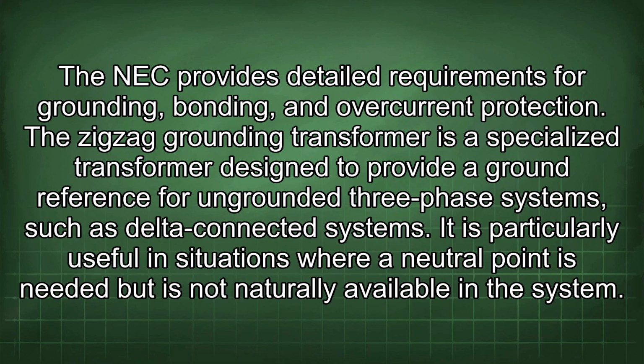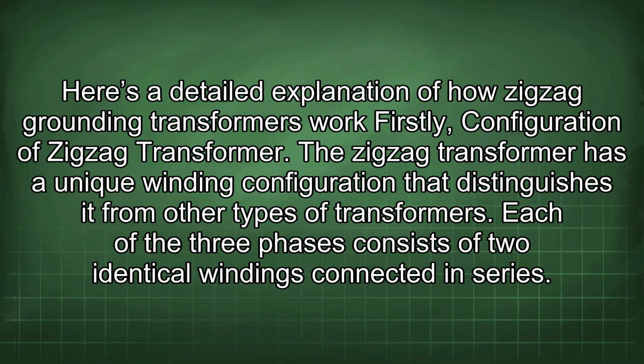The zigzag grounding transformer is a specialized transformer designed to provide a ground reference for ungrounded three-phase systems, such as delta-connected systems. It is particularly useful in situations where a neutral point is needed but is not naturally available in the system. Here's a detailed explanation of how zigzag grounding transformers work.